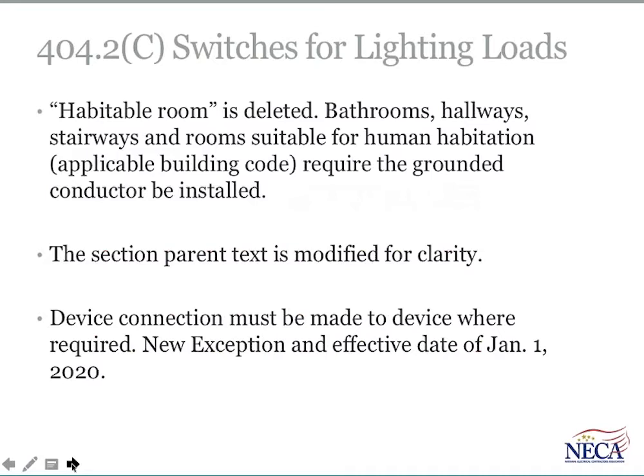The phrase habitable room was deleted, which essentially expands the requirement for bringing the grounded conductor to switch locations, areas like bathrooms, hallways, and stairways, and so forth. And the whole idea there is to have a neutral conductor to connect the appropriate rated motion sensor that typically requires a neutral conductor to operate the brains of the device. The next thing you'll notice as a change in that section clarifies that the device connection must be made to a device where required. The change there was necessary because the previous rules only required that you bring the grounded conductor or neutral to those switch locations. It never talked about utilizing it, and that's been fixed in the 2017 NEC.